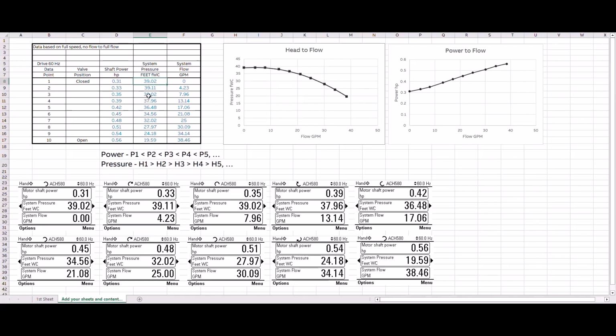What we do is we take care of this issue right here by putting a number in place. I'm looking at 39.02, then 39.11. So I'm just going to go to 39.20 and enter that as my data point. Now I follow the rules. So this will be the data that we enter into the drive. We have multiple ways of entering into the drive, and we'll go through those in a moment.